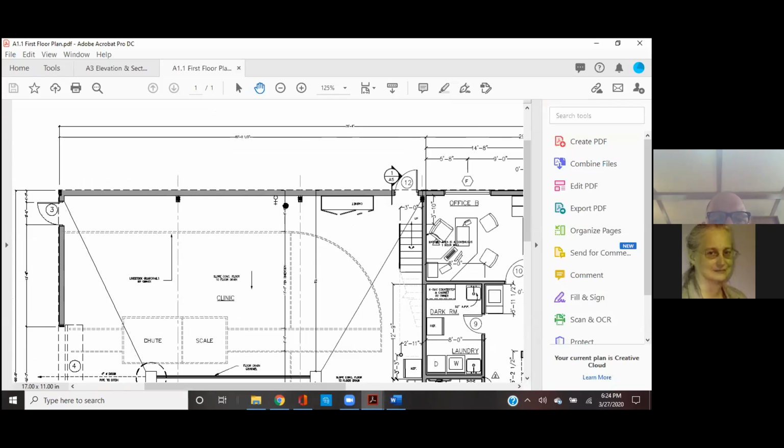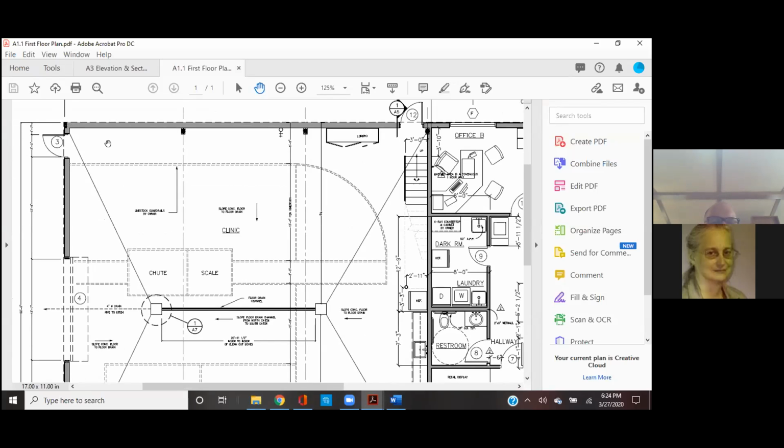So you were thinking like maybe 1, 2, 3, 4, and then maybe have a shorty going in here or something? No, that isn't what I would do at all. I would go to that first duct and put 2 by 2 kind of in the middle of that stall area. 1 in the middle by the door, 2 in the bottom part of that bay. So that bay is going to get divided into 3 parts. 2 go in where the animals are, 1 goes in where the door is, 2 go where the animals are at the bottom. Okay, so where are your first 2, over here?